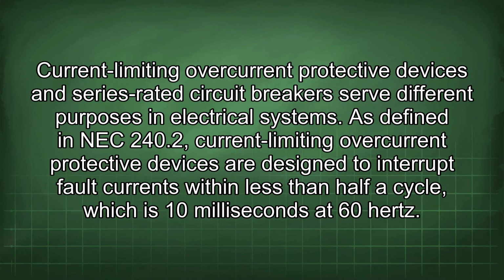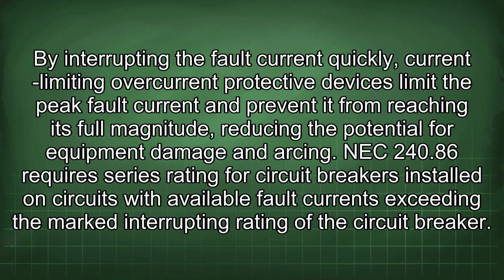Current-limiting overcurrent protective devices and series-rated circuit breakers serve different purposes in electrical systems. As defined in NEC 240.2, current-limiting overcurrent protective devices are designed to interrupt fault currents within less than half a cycle, which is 10 milliseconds at 60 Hz. By interrupting the fault current quickly, current-limiting overcurrent protective devices limit the peak fault current and prevent it from reaching its full magnitude, reducing the potential for equipment damage and arcing.